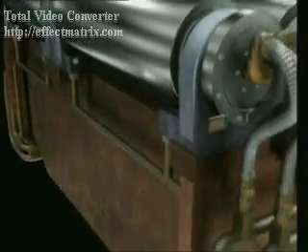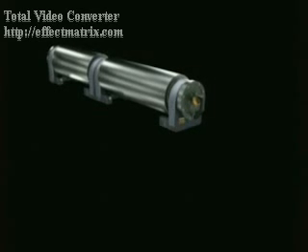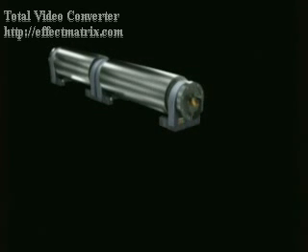The BHE unit is placed inside the bearing housing, which is then secured against the intrusion of water and steam. The BHE is connected to the RSE unit with heat-shielded wires. The analog measuring data is calibrated and transformed into a digital signal within the BHE. This way, the signal stays uncorrupted and is not affected by heat or electrical disturbances.